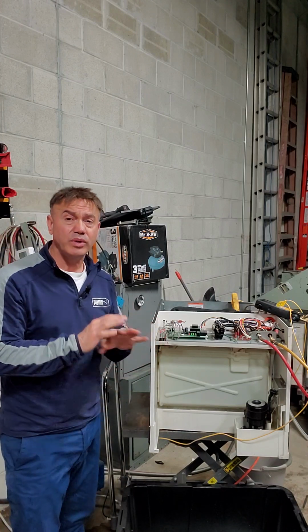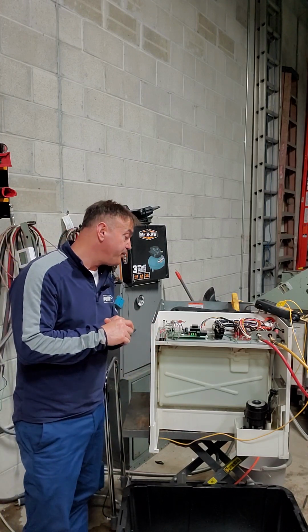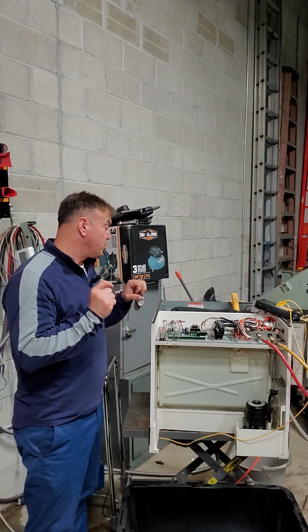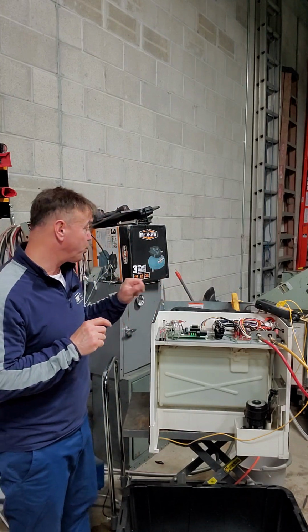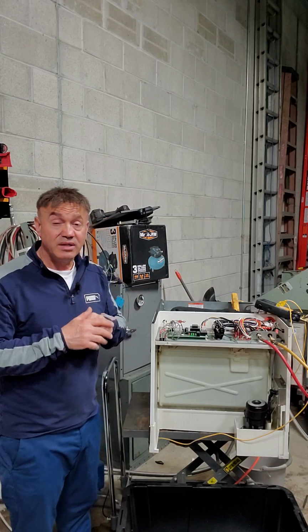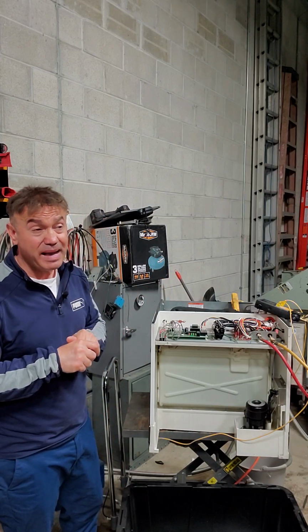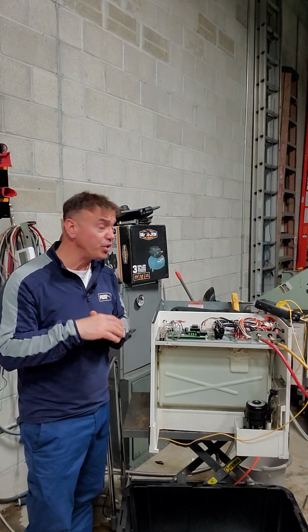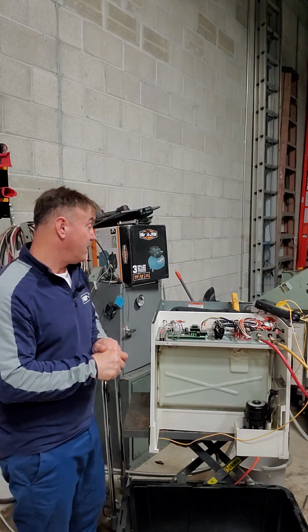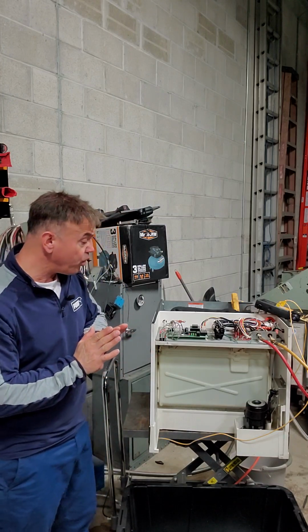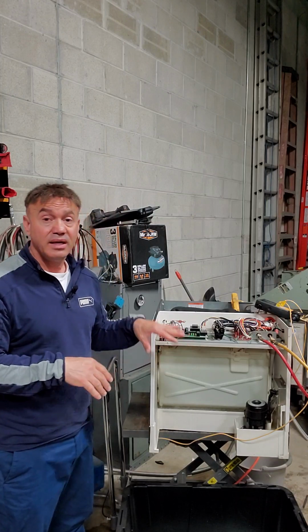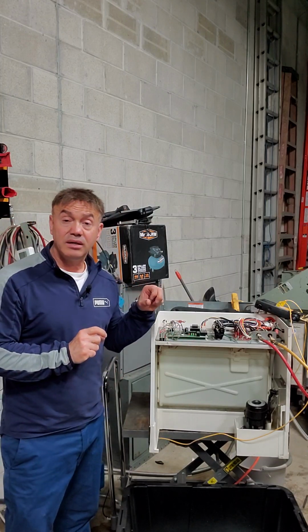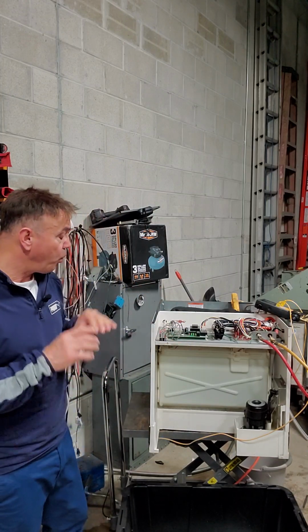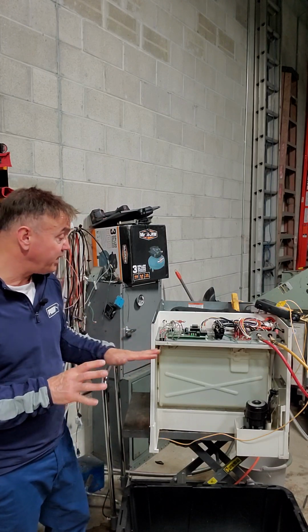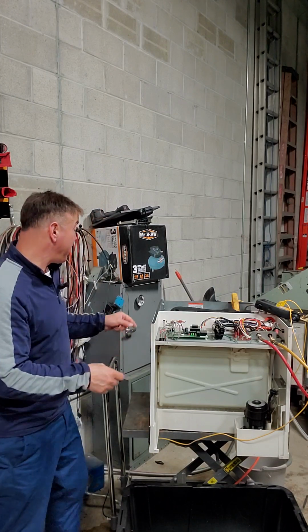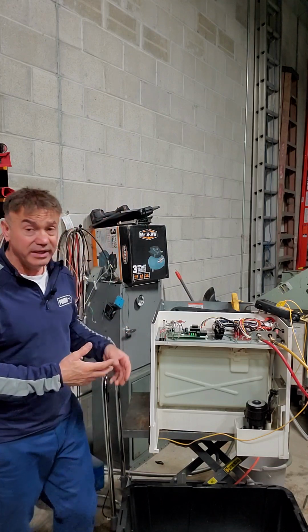Now the control board will do several things. First of all, it will turn off the condenser fan. It will turn on or open the hot gas bypass valve I showed you earlier. At the same time, it will flush whatever water remains in the pan, and it will stop the pump, the water pump assembly. No more water circulating, and then the bypass by itself will warm up the evaporator again, right?